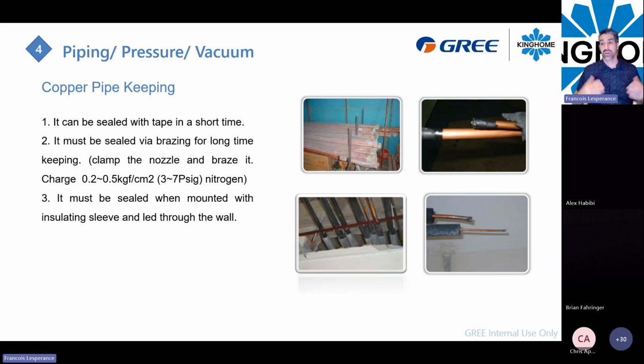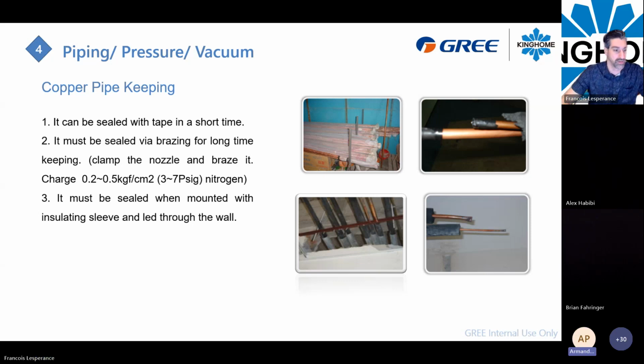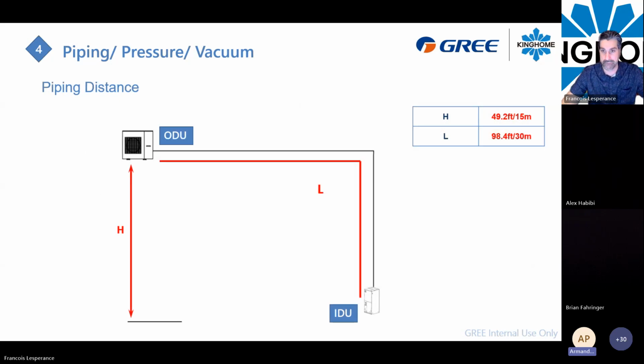Sorry to interrupt there. So 49 feet max height. If we're within max line set length, can we just install an oil return trap there, or no? 49 feet is maximum. Like proper refrigerant piping practices dictate we can put in an oil return trap there, but because it's a heat pump, it has its own oil return mode, and then you don't have to add traps because the pressure is high enough to bring back the oil inside the compressor. So 49 feet is maximum, regardless of our refrigerant piping practices. It is what it is, no matter what. Yes. Got you. Thank you. No problem.